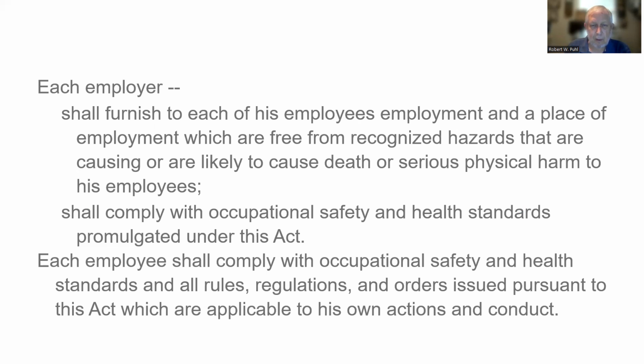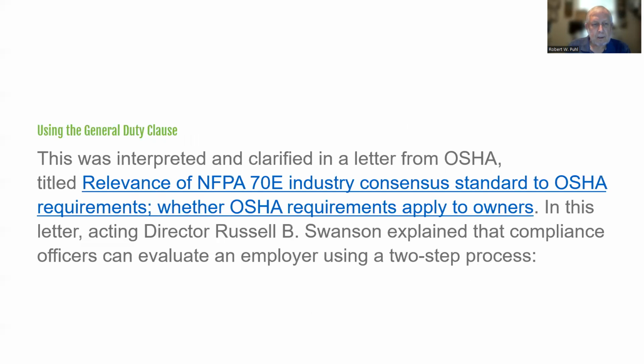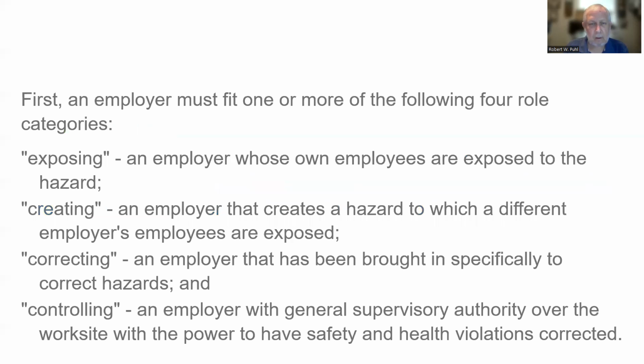Remember, the employer has to provide a place of employment free from recognized hazards. This was interpreted and clarified in a letter from OSHA titled Relevance of NFPA 70E Industry Consensus Standard to OSHA Requirements, addressing whether OSHA requirements apply to owners. In this letter, Acting Director Russell B. Swanson explained that compliance officers can evaluate an employer using a two-step process. This came from the director now of OSHA.